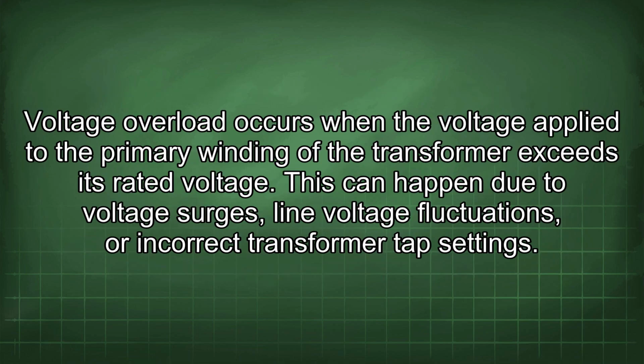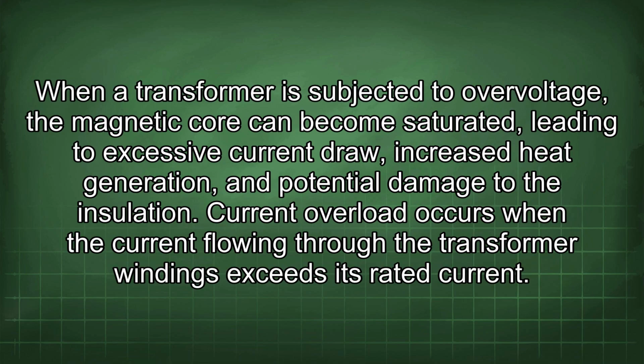Voltage overload occurs when the voltage applied to the primary winding of the transformer exceeds its rated voltage. This can happen due to voltage surges, line voltage fluctuations, or incorrect transformer tap settings. When a transformer is subjected to overvoltage, the magnetic core can become saturated, leading to excessive current draw, increased heat generation, and potential damage to the insulation.